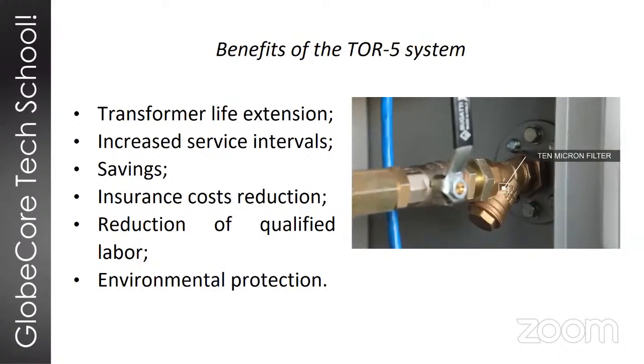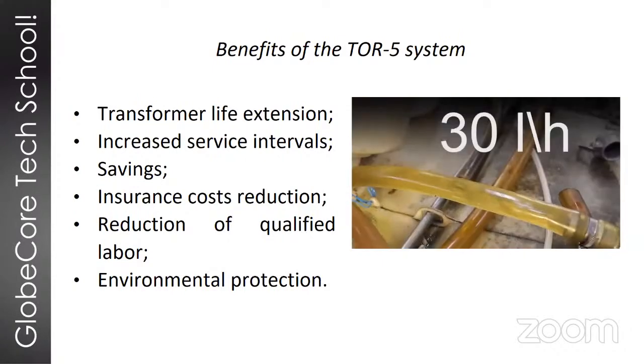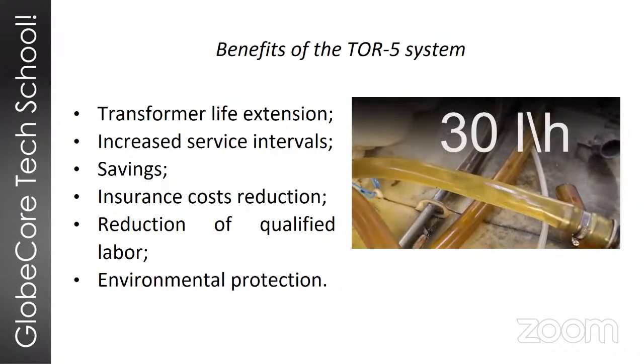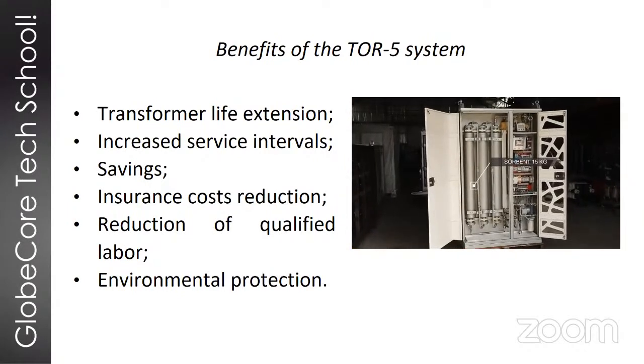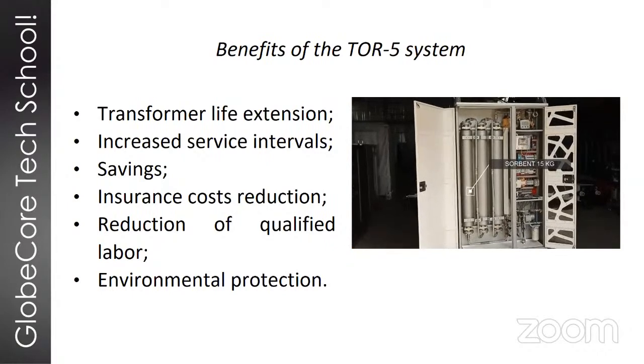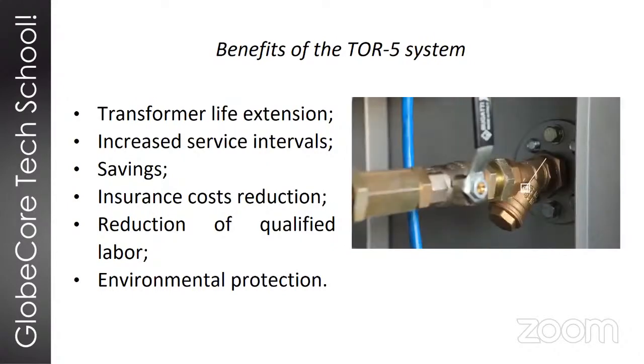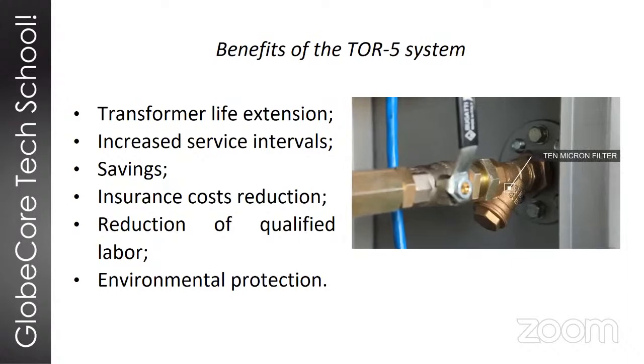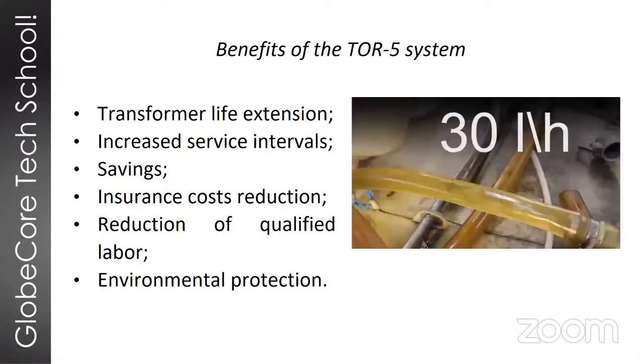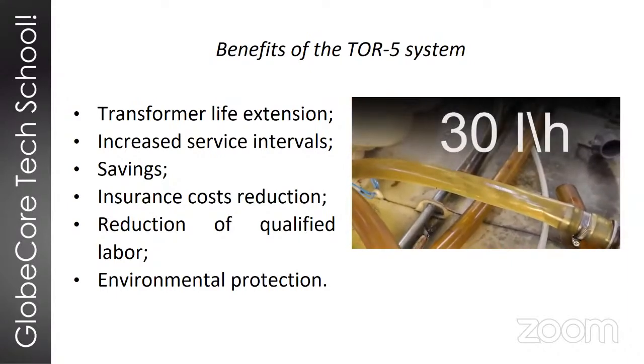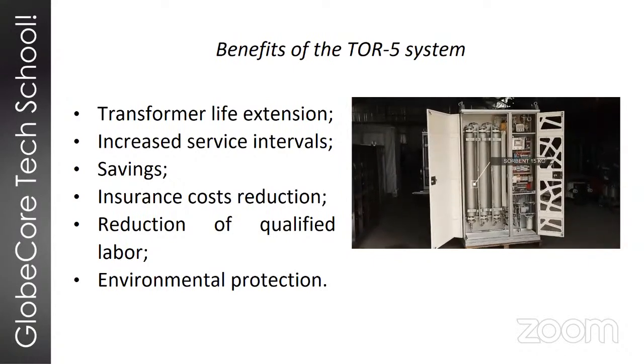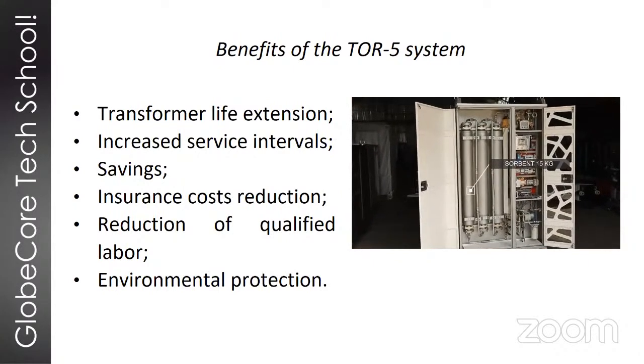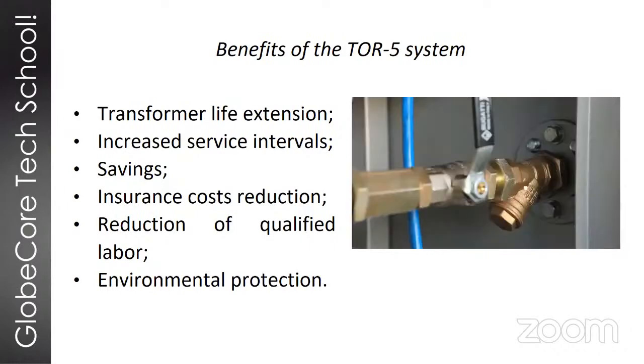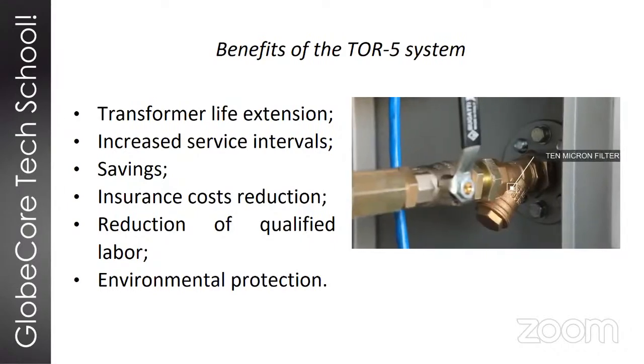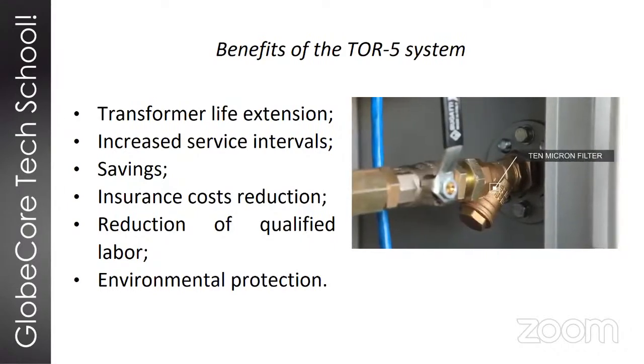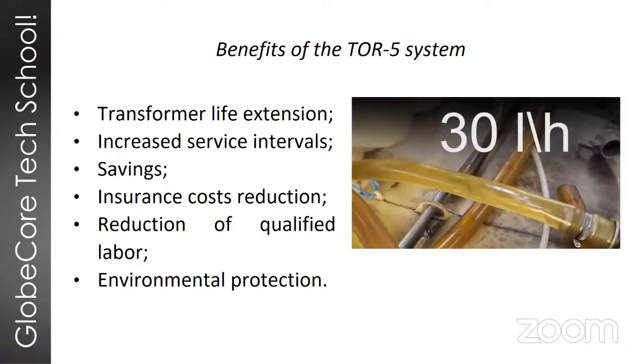Right, so this system is great, and let's summarize why it's great. What it does is, using the TOR5 system, extends the transformer lifetime by dozens of years. For older transformers, the TOR5 gives us an indication of just how old the oil in the transformer is, and it gives us a good indication when we need to start repairing the transformer, or in the worst case, when we need to shut it down and decommission it before we have a catastrophic event in the transformer.